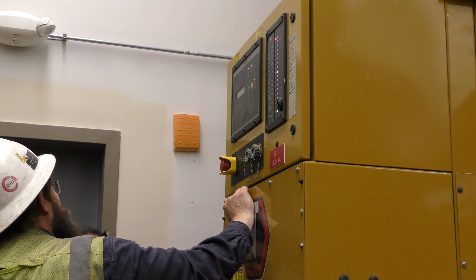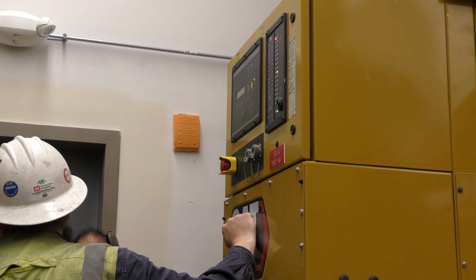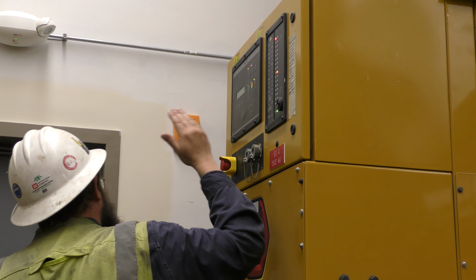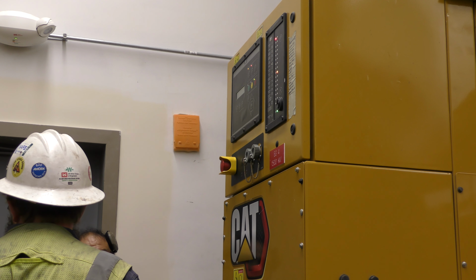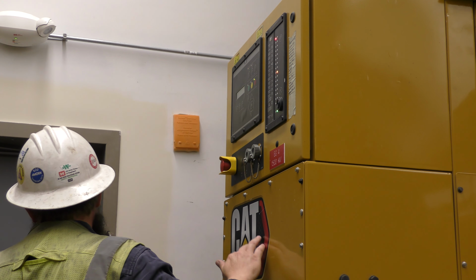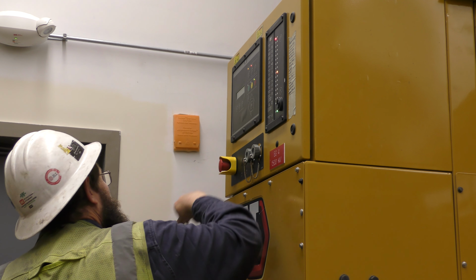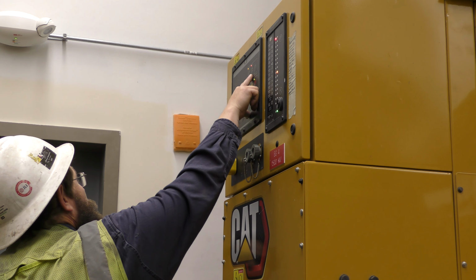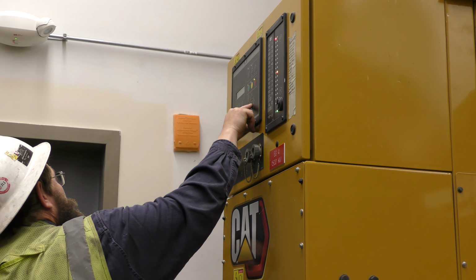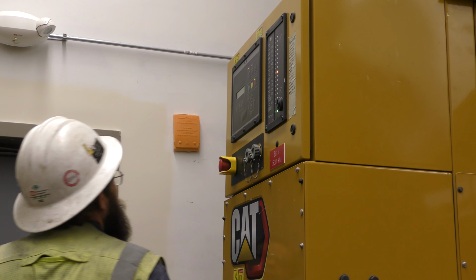We used to get callouts all the time from customers, so someone hits the e-stop to shut it off, and then they can't get the thing to start. So any shutdown, once the problem's corrected, so you have low oil pressure, figure out what's wrong with it, or the e-stop's hit, any shutdown will lock this thing out. You have to reset it. So with the e-stop, you've got to make sure to bring the e-stop back up. You go to the reset button. It's going to ask you to reset all events. Okay, red light's gone. You can fire this thing back up.